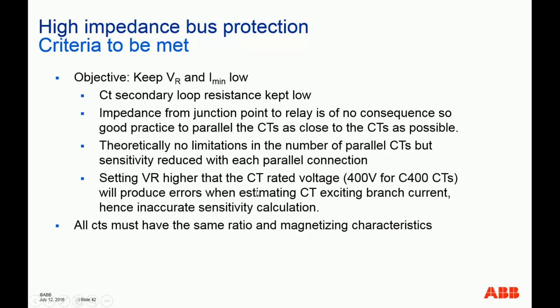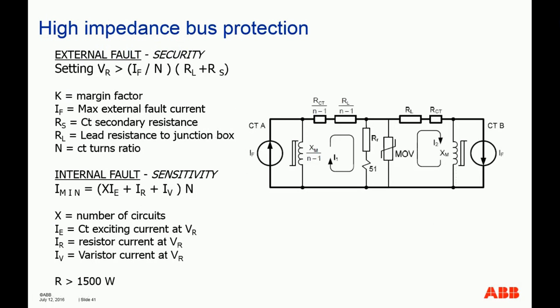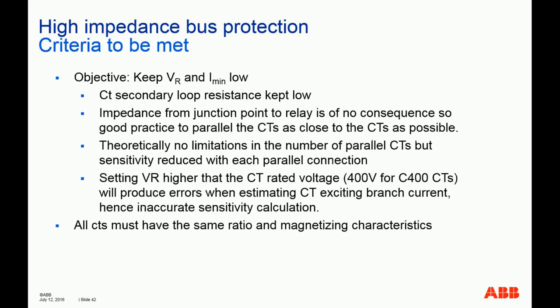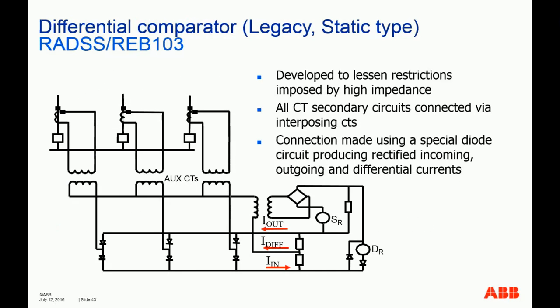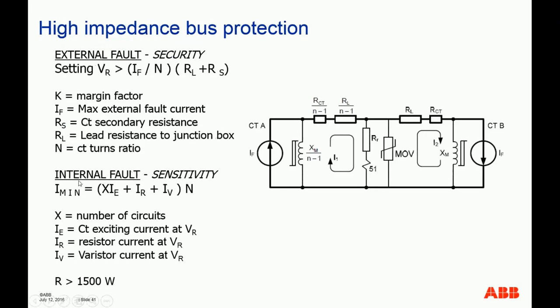This is from a paper I read many years ago. It's a very good paper from WPRC. If you set VR, which is your protection setting here, higher than the CT rated voltage, for example, 400 volts for the C400 CT, 800 volts for the C800 CT, it will produce error when estimating the CT exciting branch current. That is, when you are calculating the exciting currents here, you usually estimate them using the CT excitation curve that I showed you earlier.